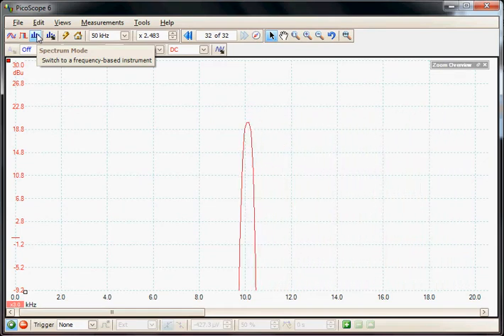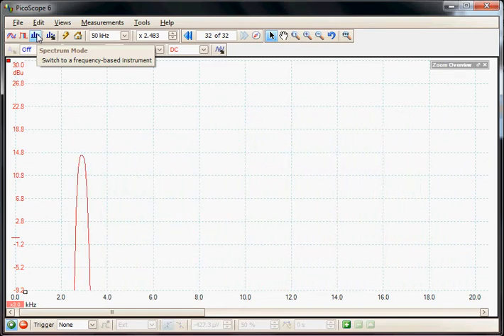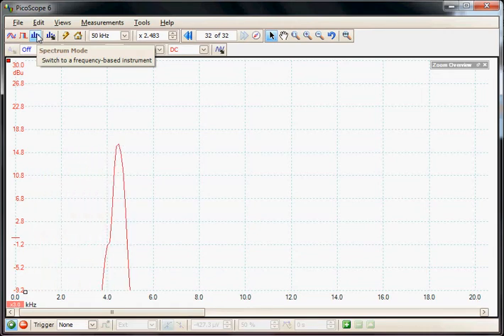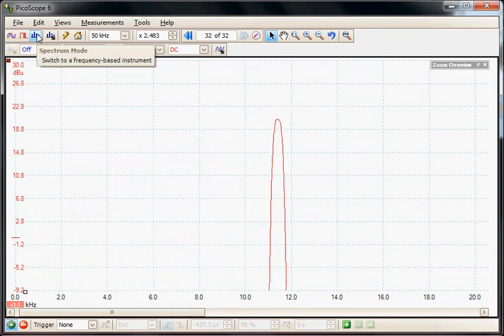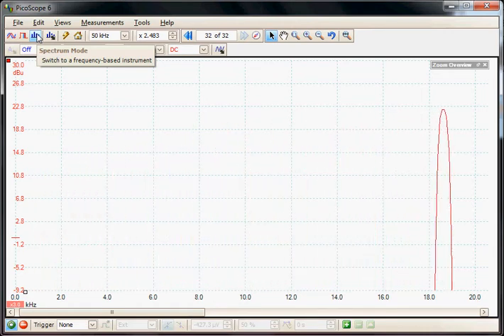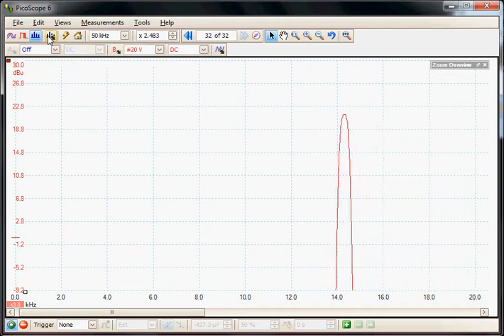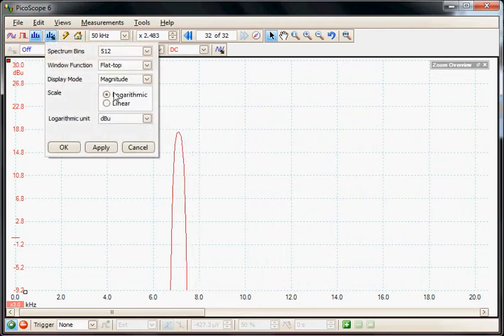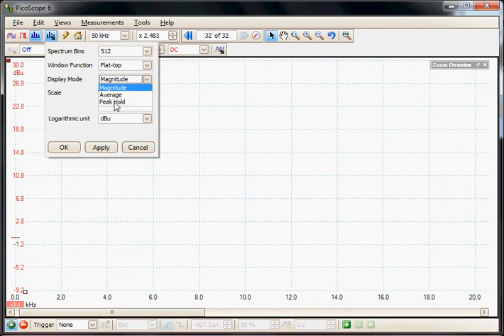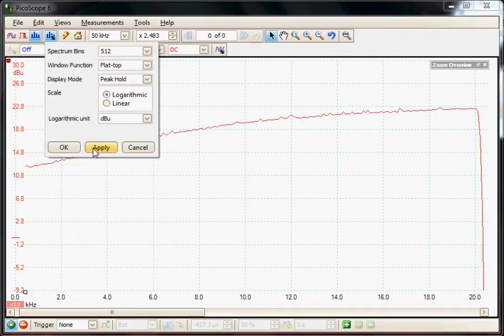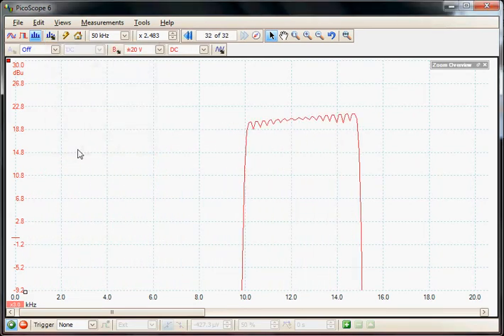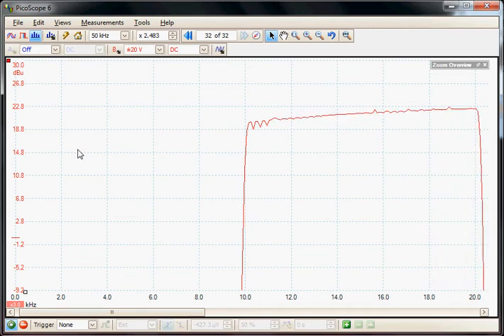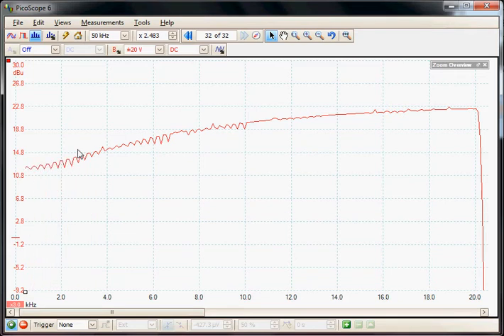Here we can now see the sweeping frequency and we can almost just visually see now that the amplitude is increasing as it goes up in frequency. Further we can actually change the settings to hold the max value and I'll apply that. Now we get a very clear visual indication of the frequency response of the device under test.